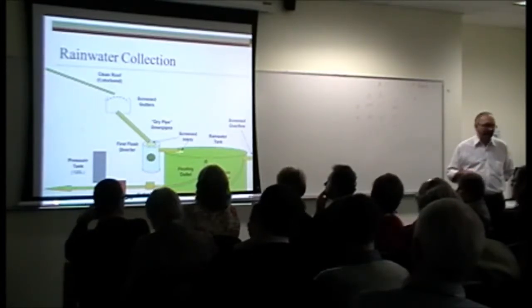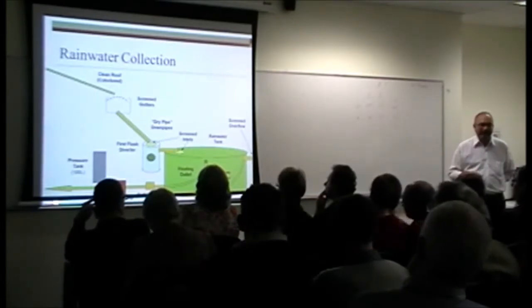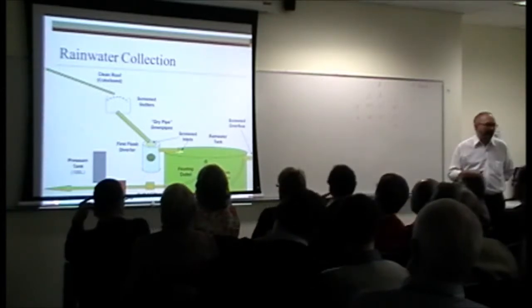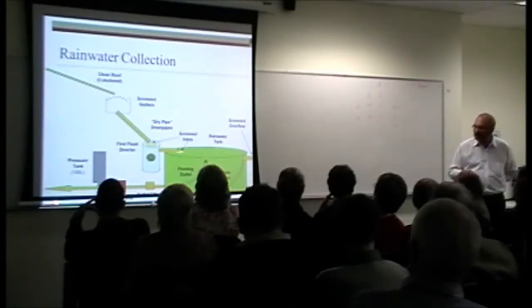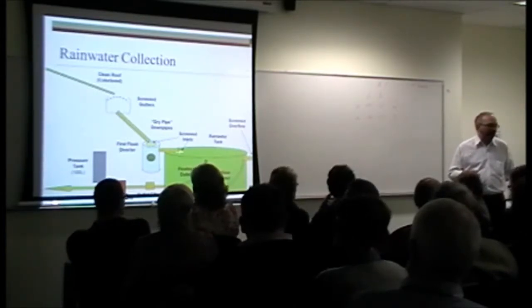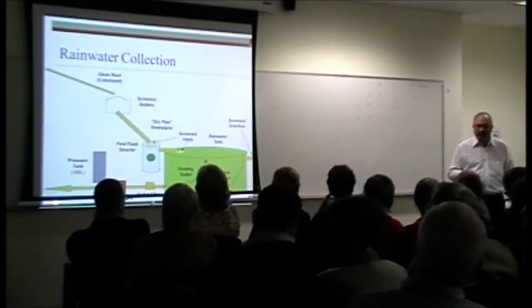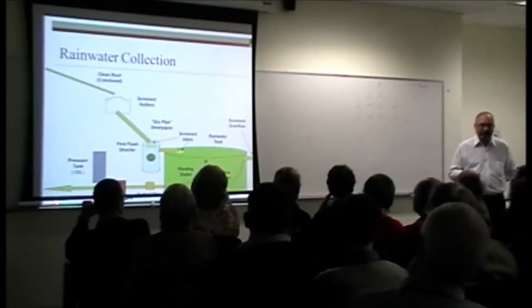So in an ideal world, you'd have a nice big header tank up the hill and pump up to there once every few days, and then live the rest of your life under gravity feed. And we have friends who have precisely that. We don't quite have that luxury, but a nice big pressure tank is sort of like a personal hill. So it allows you to reduce the number of pump starts, and instead of starting up half a dozen times a night, we see it starting up maybe once. So it's noticeable and it makes a difference.